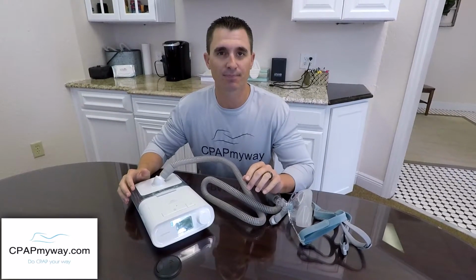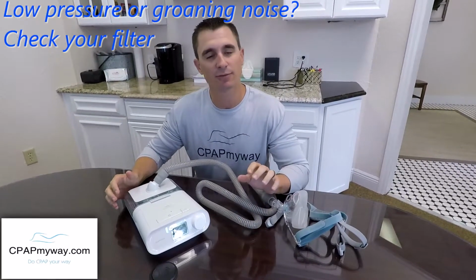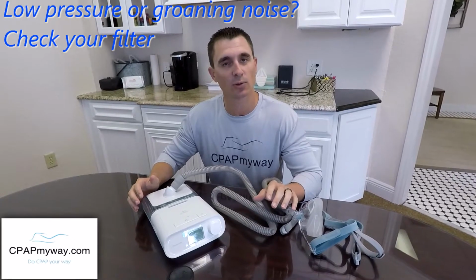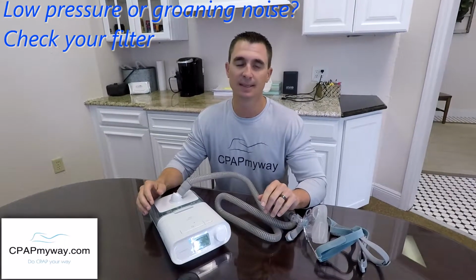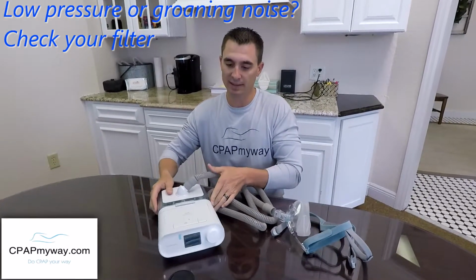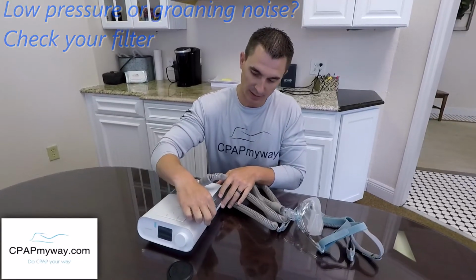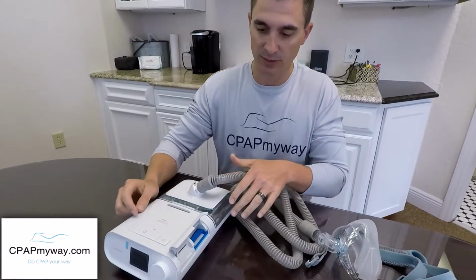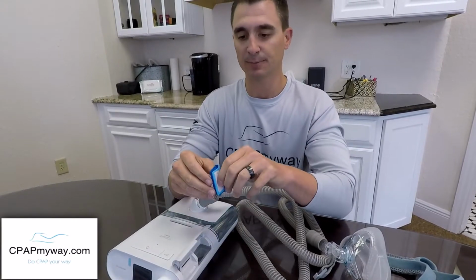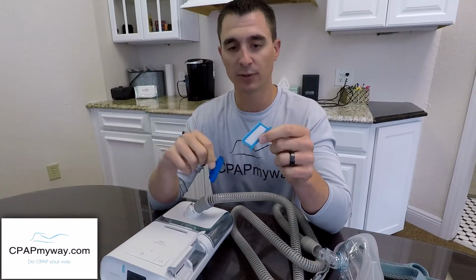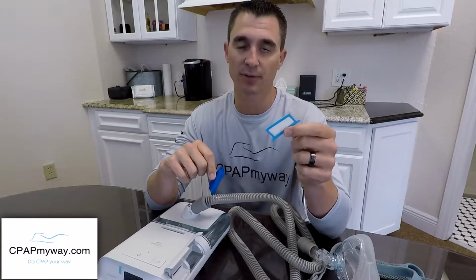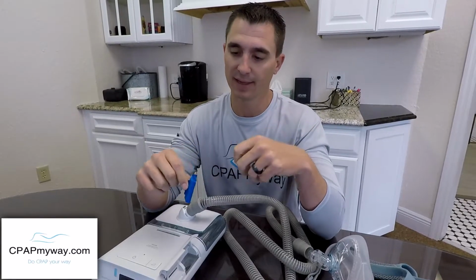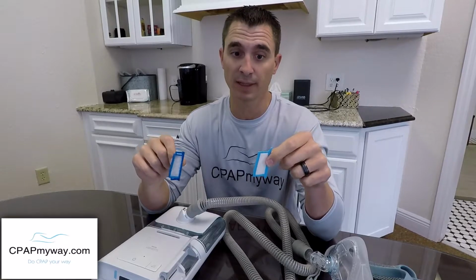The final thing we hear is a groaning noise, or they don't feel like there's enough pressure coming out anymore and nothing's changed on the settings. That is almost always a filter issue. For instance, on this DreamStation, there's a little filter housing right here. It has a disposable and a reusable filter. Your disposable filter has got to be thrown away at least once a month, and the washable filter needs to be rinsed out once a week. If you're not doing that, start doing it.